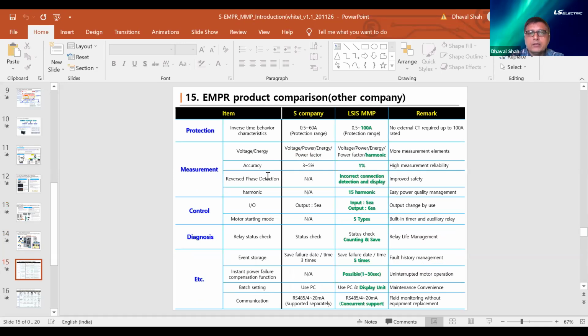So again, coming back to the products, what is the difference? We have up to 100 ampere, from 0.5 to 100 ampere. Voltage level, we have the harmonics monitoring in the same relay. We have accuracy class of 1%. We have incorrect connection detection. Generally, if there is a reverse phase connection or the connections are not proper, that is also detected and displayed on the same. Harmonics you can monitor up to the 15th harmonic.